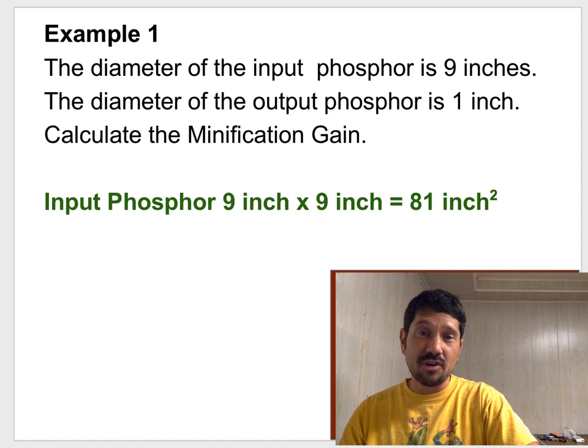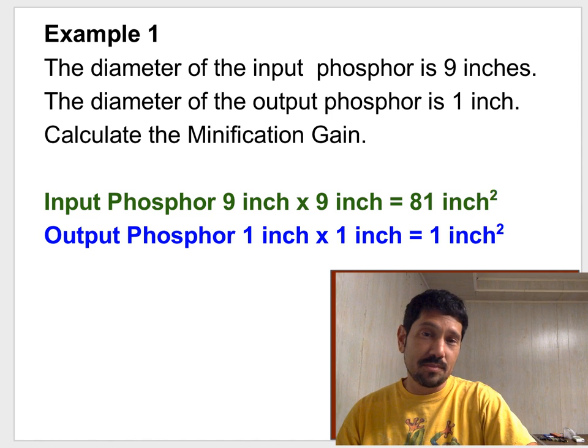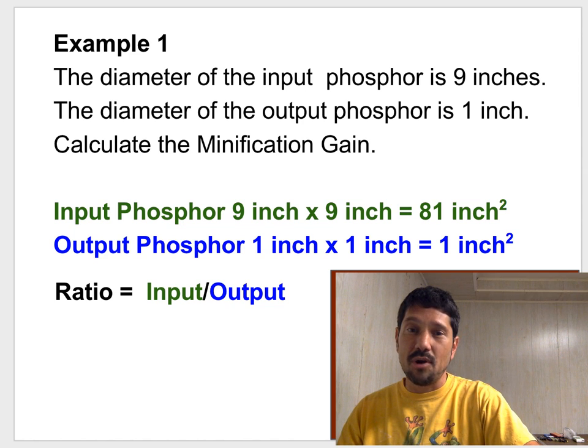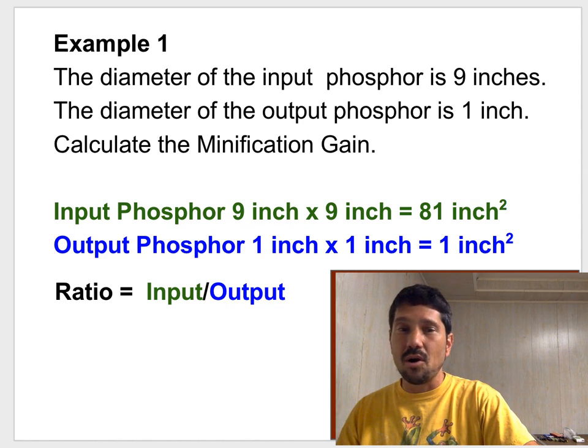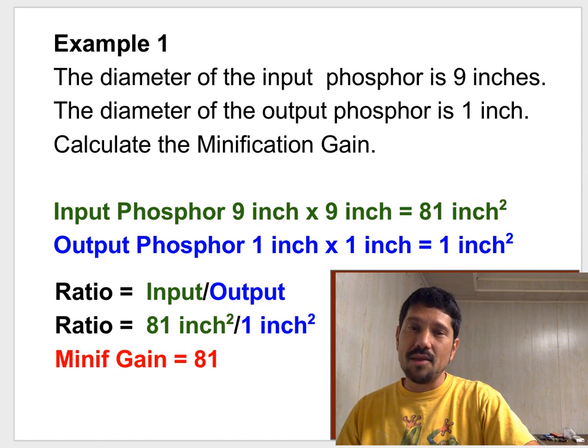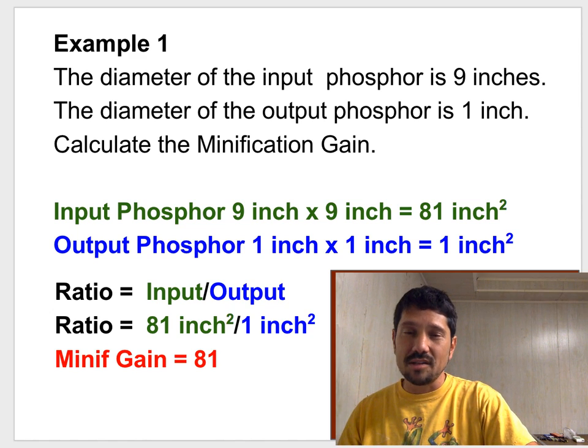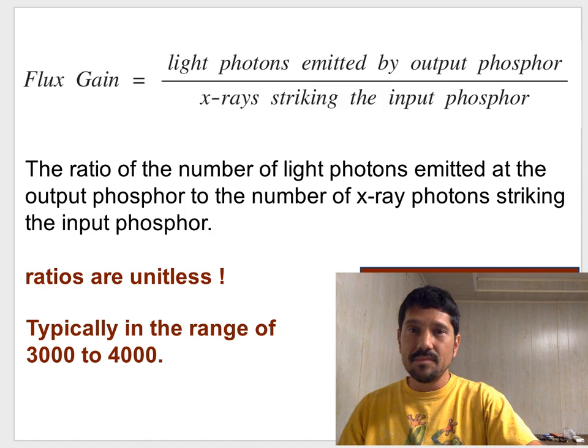An example would be you have an input phosphor of 9-inch diameter and an output phosphor of 1-inch. Calculate the gain. So the input phosphor, you'd take 9-inch by 9-inch to get 81-inches squared. The output phosphor you would multiply by itself to get 1-inch squared. And for the minification gain you would put the input over the output. The big number over the small number. And you would end up with 81-inches squared over 1-inch squared resulting in a minification gain of 81. And they're unitless.